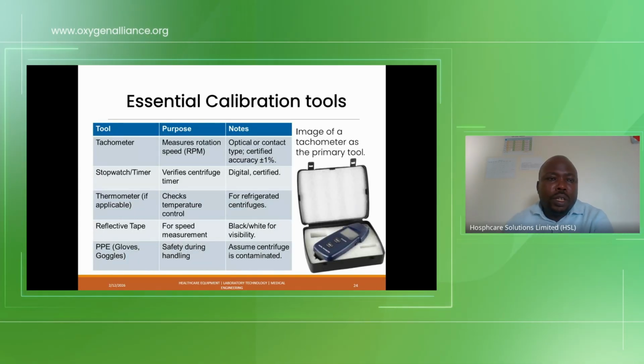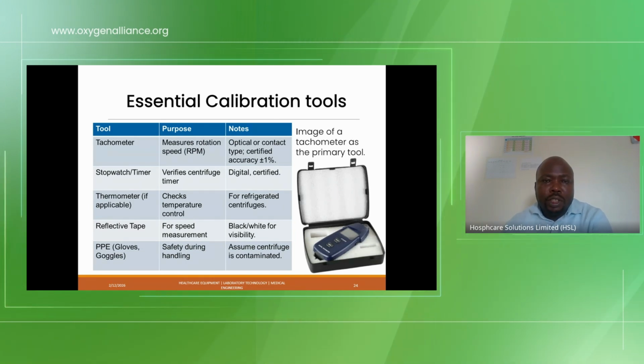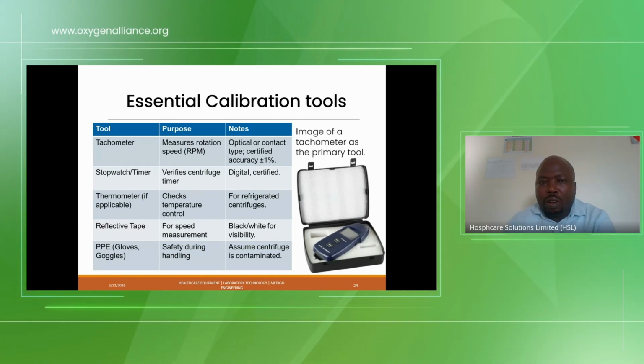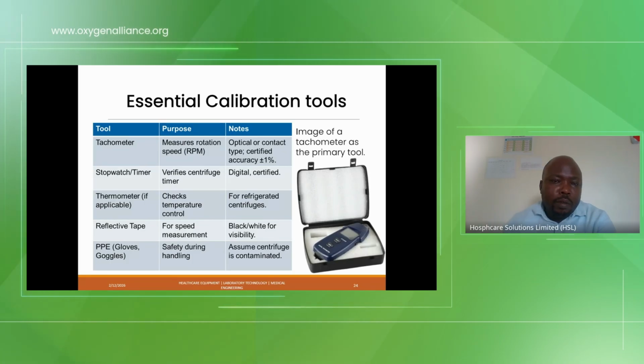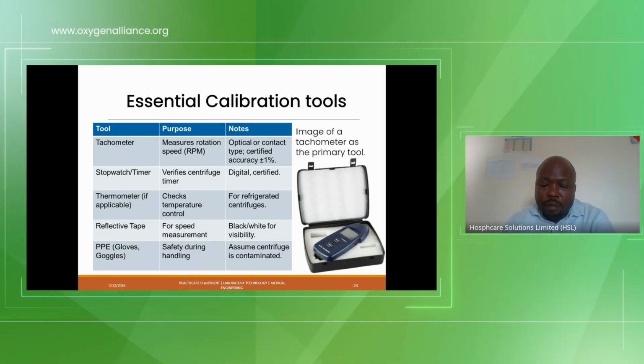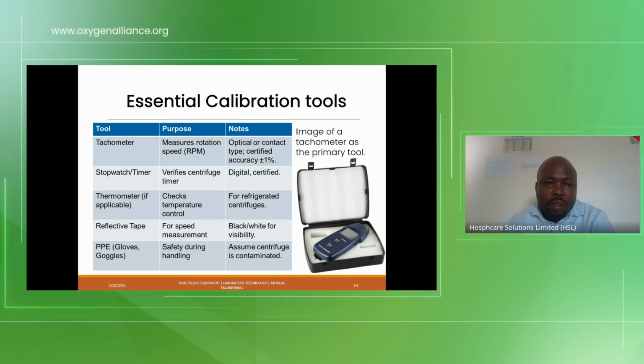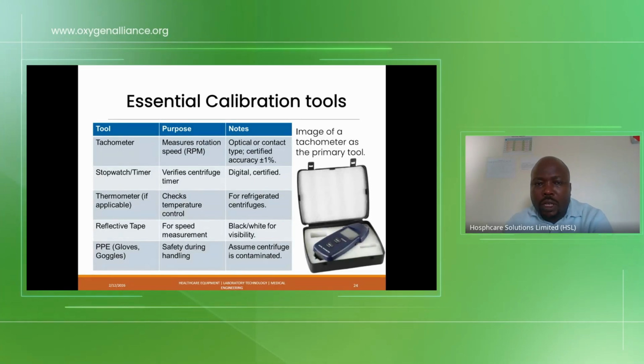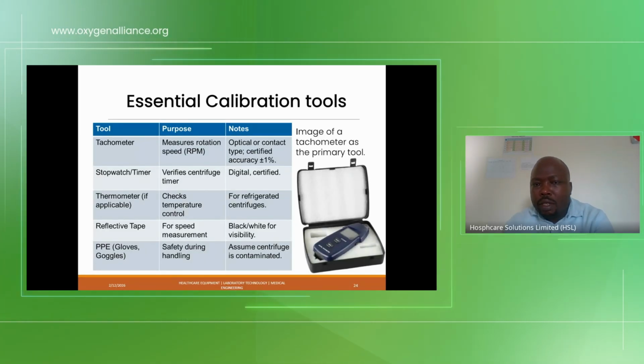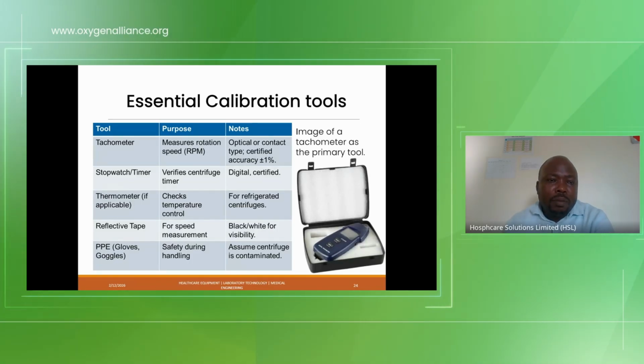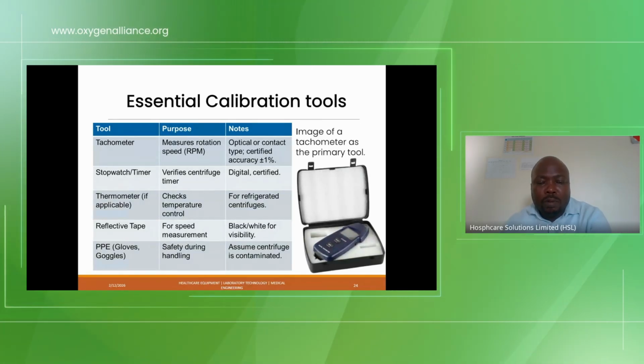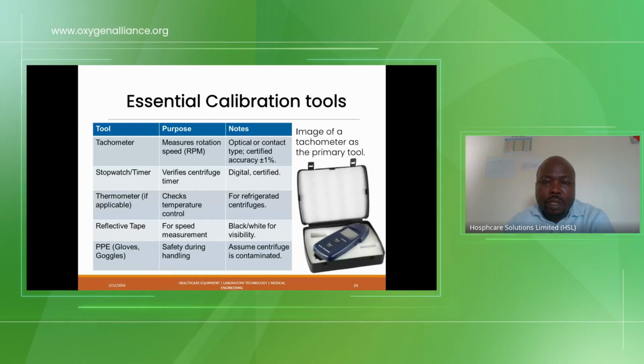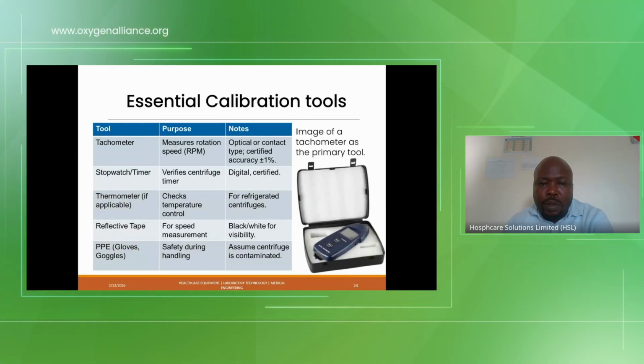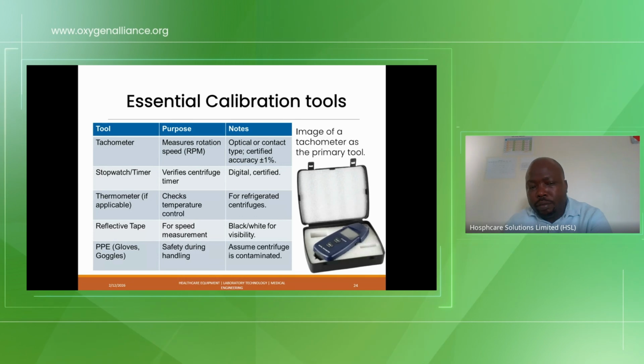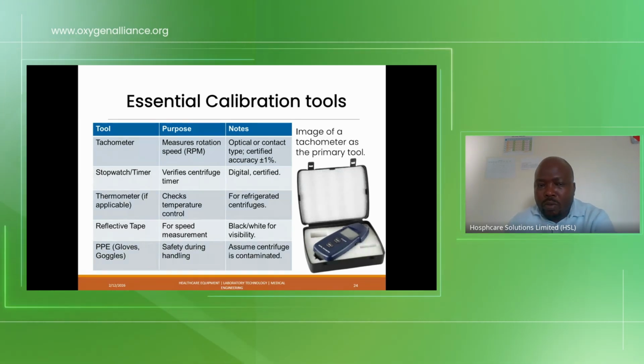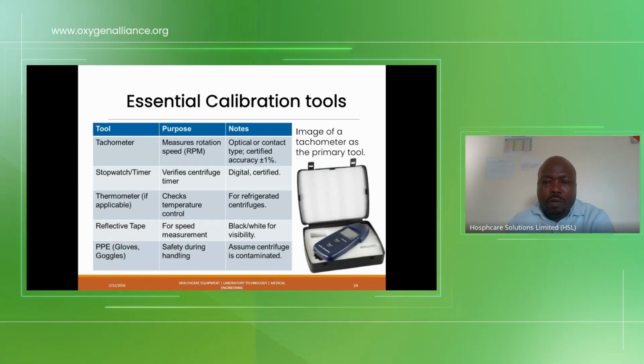Essential calibration tools you need: a tachometer, whose purpose is to measure rotation speed, optical or contact type, with certified accuracy of plus or minus 1%. You need a good working stopwatch or stop timer to verify the centrifuge timer, digital or certified. You need a thermometer applicable for refrigerated centrifuge machines. You need reflective tape for speed measurement. You need PPE, that is gloves and goggles, when you are doing your test for your own safety.